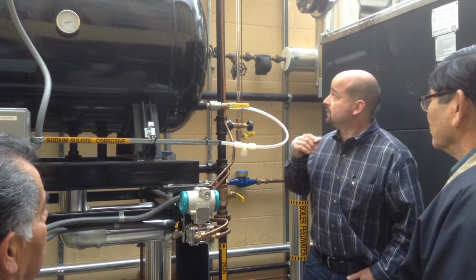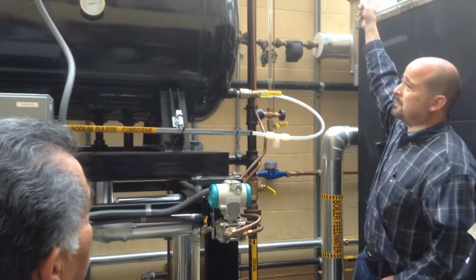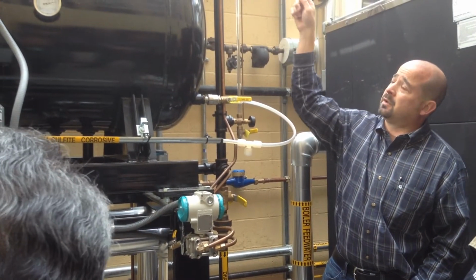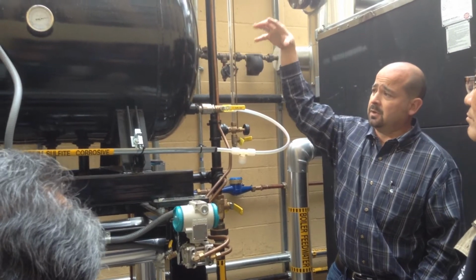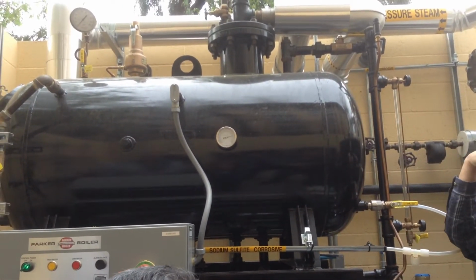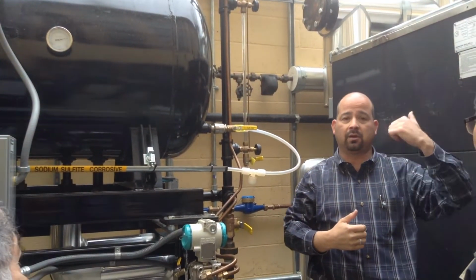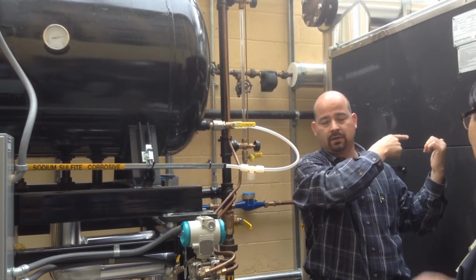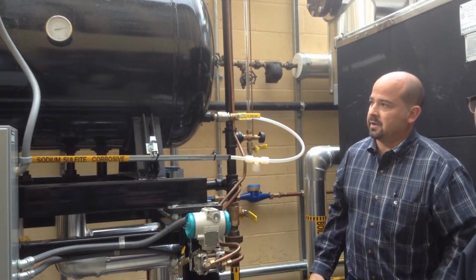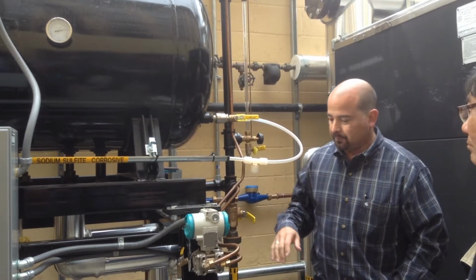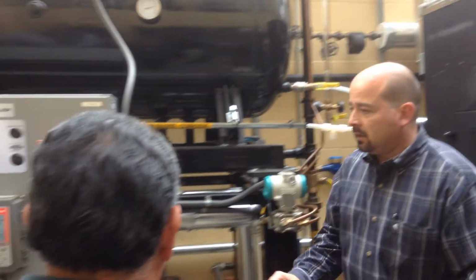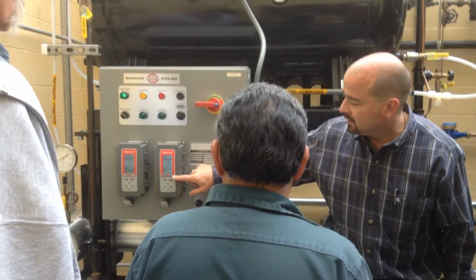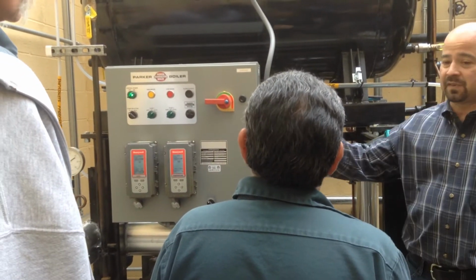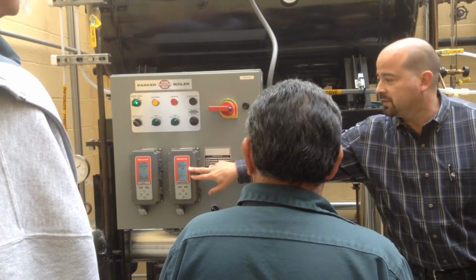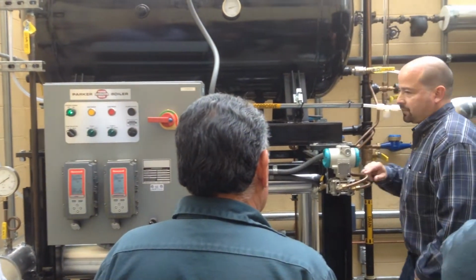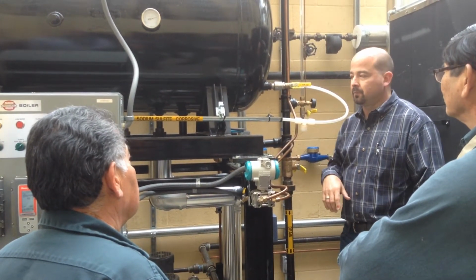So the way we heat it is there's a steam line right here that comes off of the main steam header. It gets injected into a spray head and goes down into the deaerator. So you have steam mixing with water and potentially condensate return coming from, I think you have a condensate return transfer pump in the other building there. It mixes together and goes into the deaerator, reducing the oxygen levels. So we talked about water level. Steam control is based on temperature here. You have a temperature sensor inside the tank, and that goes to this T775, and that's what controls what temperature we want to maintain in the tank. We obviously don't want to get too hot.